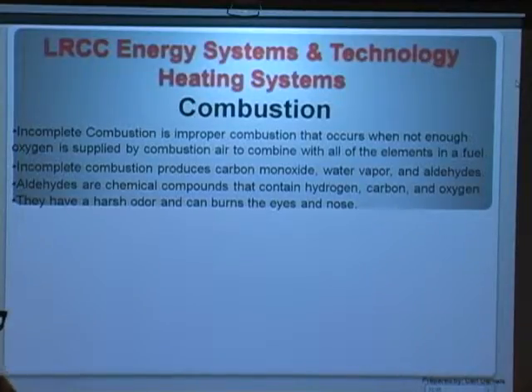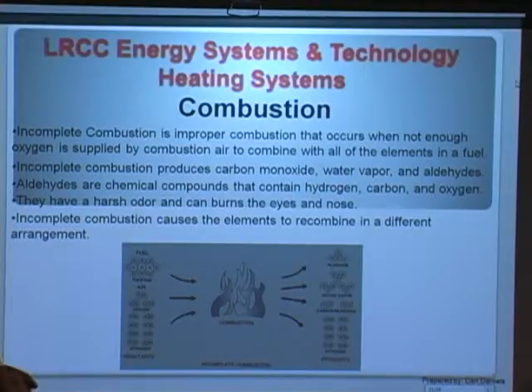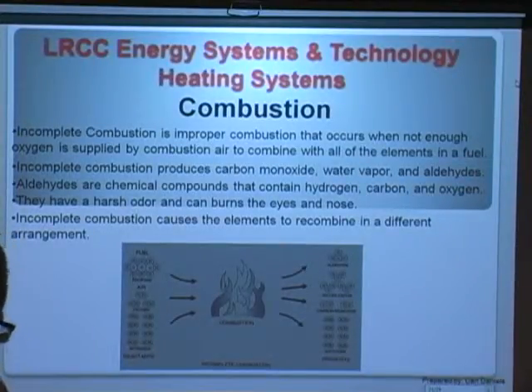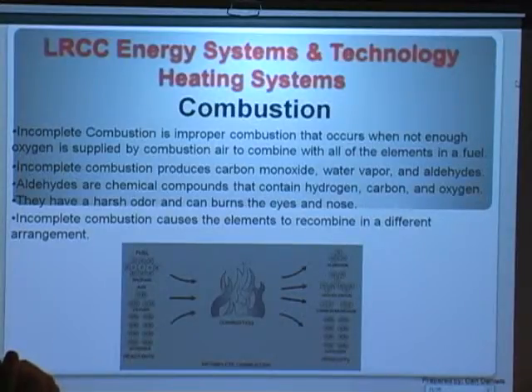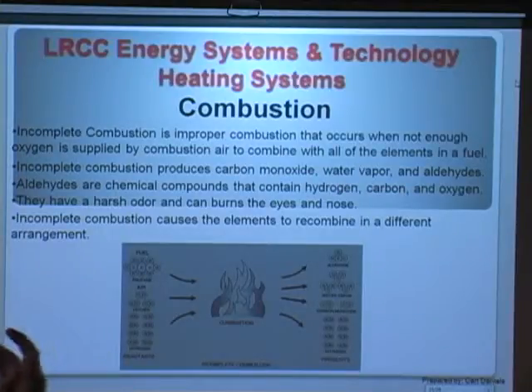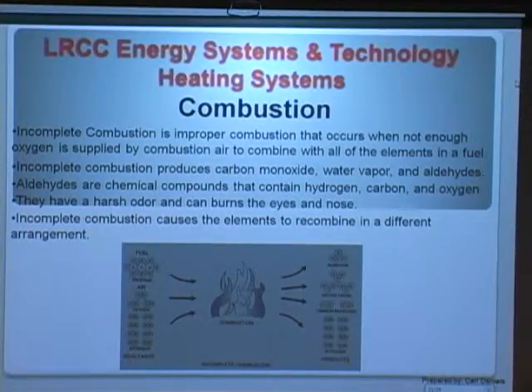That harsh metallic taste and slight burning in your eyes and nose — that's the aldehydes. Remember, carbon monoxide you cannot taste or sense. You start developing symptoms: nausea, stomach ache, sleepiness, headaches — that's the carbon monoxide. The aldehydes, on the other hand, you can almost taste on your tongue when you walk in. I've been in homes where as soon as you walk into the basement you can tell right away the burner isn't firing right. Usually it's from oil-fired burners more so than natural gas — it takes a lot to get a natural gas flame out of whack enough to produce detectable aldehydes.